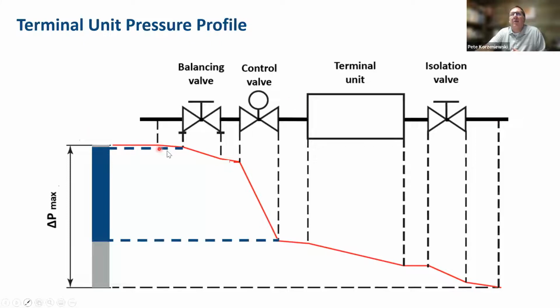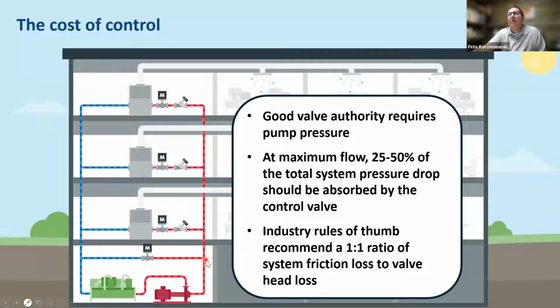So as we travel through this, 2/3 to 3/4, 70% of pressure is required for this particular terminal unit by the balancing and control. I've got a bit of loss through the terminal unit itself, and then an even lesser amount for that last isolation valve as we travel back into the system. So this is a significant amount of pressure that we need for good control of the system.